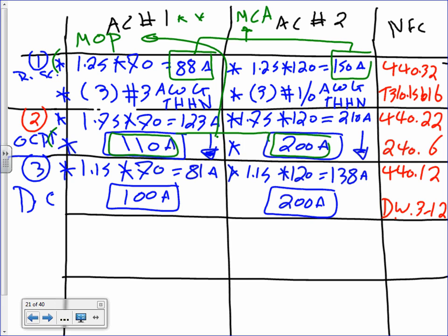The horsepower rating is if you are to come while the motor is running and you turn this motor off, you don't want this one to blow up in your face. So they have to have a horsepower rating and an amp rating. But the problem for HVAC equipment, since we don't have a horsepower, what's the horsepower for this? I don't know. Here's the amp rating, but what's the horsepower rating? I don't know the horsepower rating.